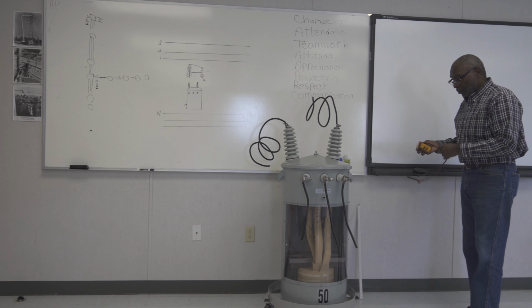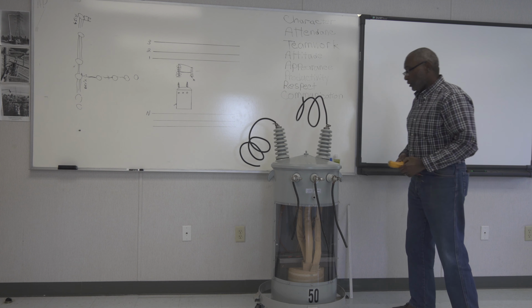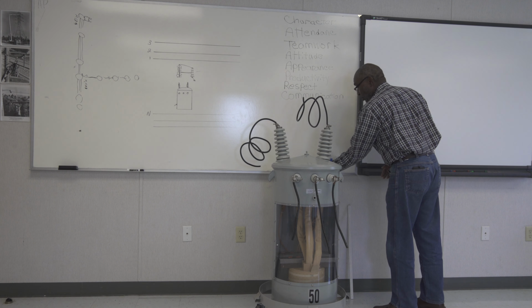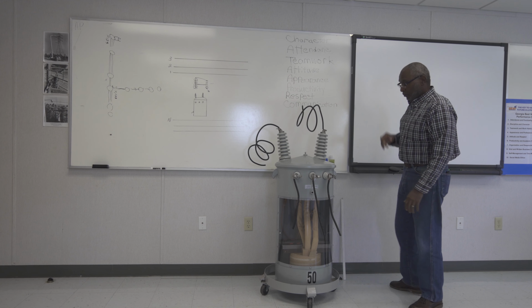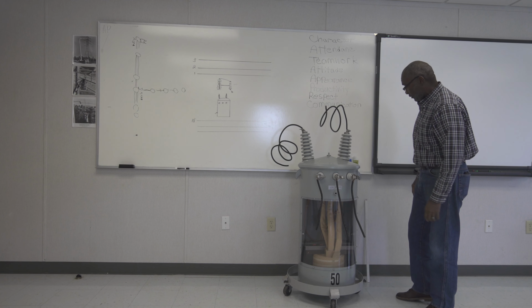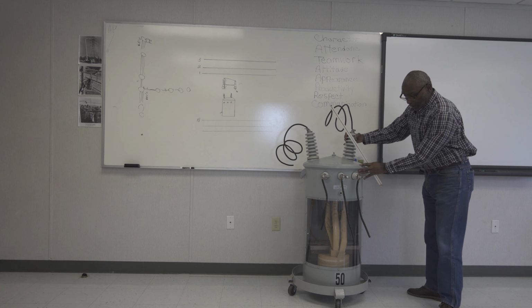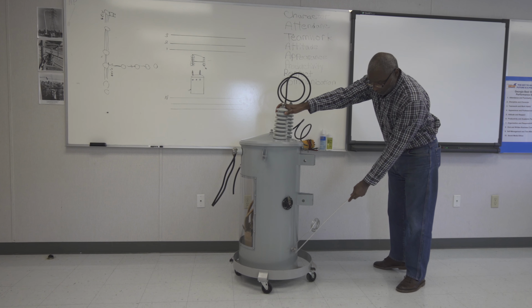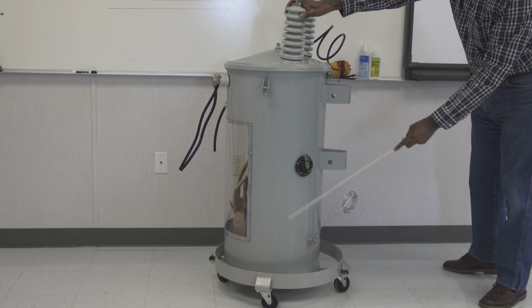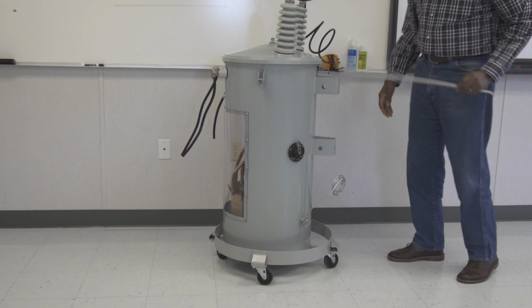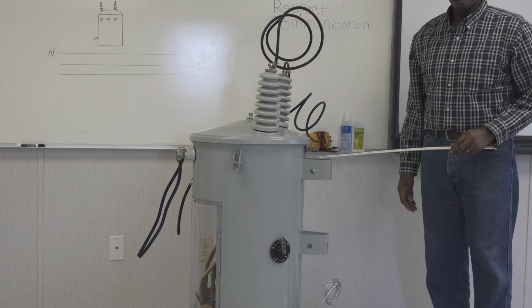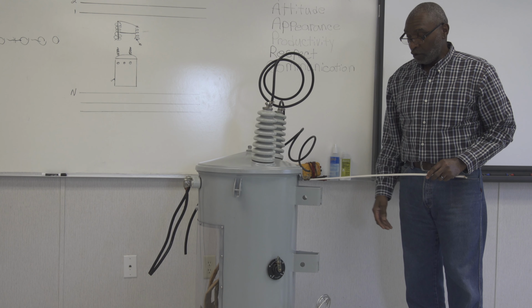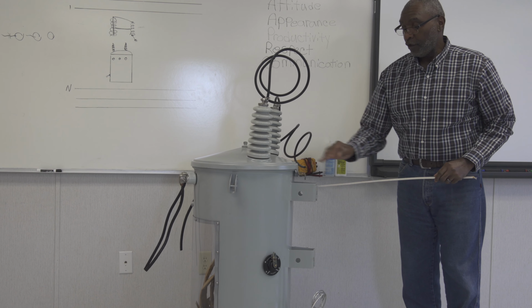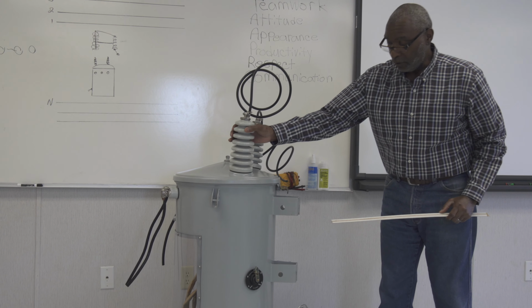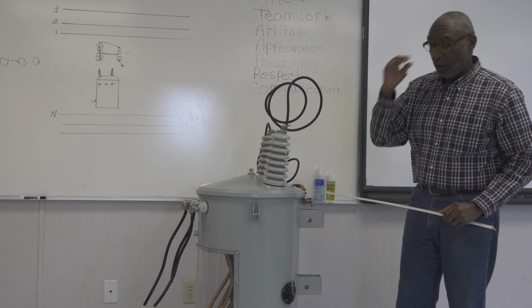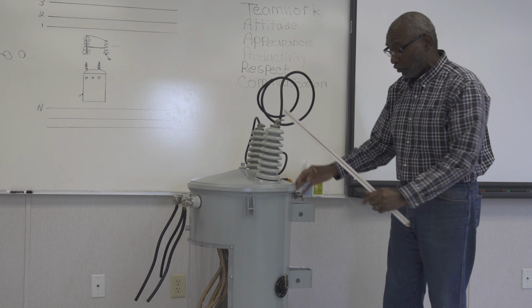Another thing you need to know about your transformer is that it has your high side and your low side hookups, as well as a hookup for your pole ground, which is considered a tank ground. You have here a bleeder for the pressure to be released off of the transformer tank. You want to make sure that anytime you're working around or with transformers, you bleed that pressure off.